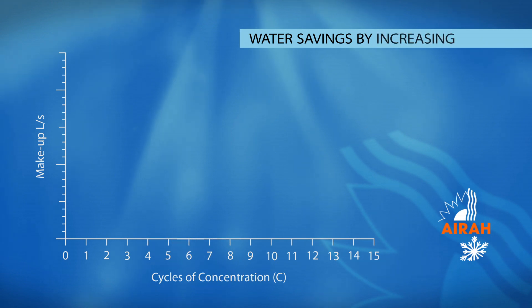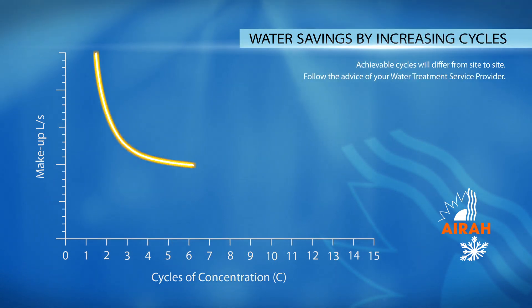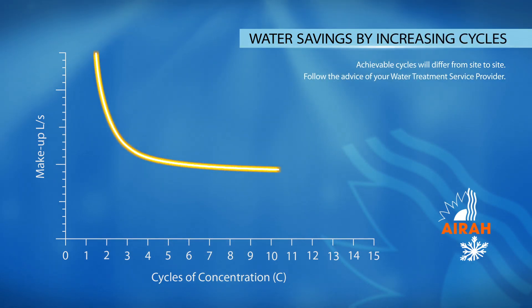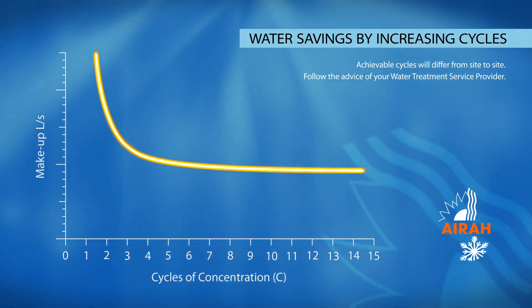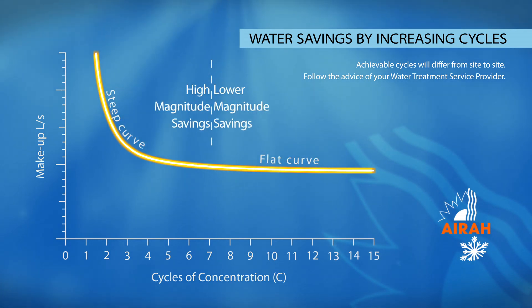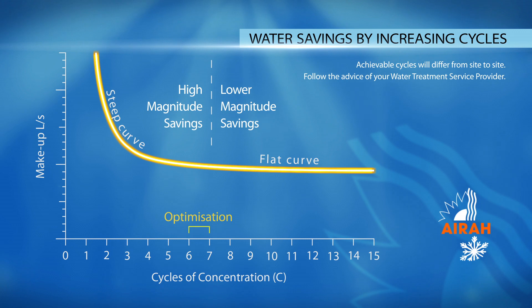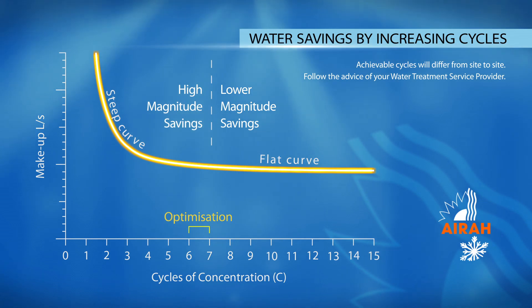Water savings achieved by increasing the cycles are not endless, as this graph demonstrates. Water savings are typically optimised at six or seven cycles before diminishing rapidly after rising above ten.